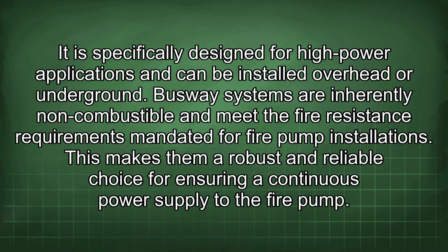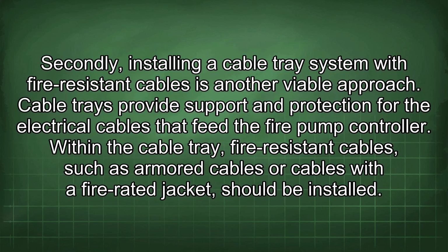Busway systems are inherently non-combustible and meet the fire resistance requirements mandated for fire pump installations. This makes them a robust and reliable choice for ensuring a continuous power supply to the fire pump. Secondly, installing a cable tray system with fire-resistant cables is another viable approach.